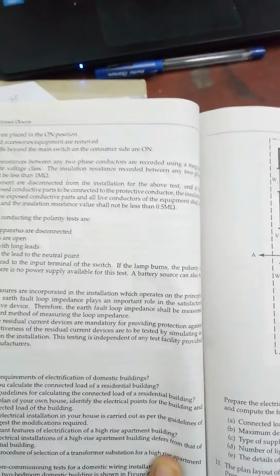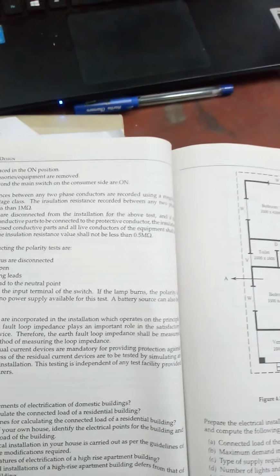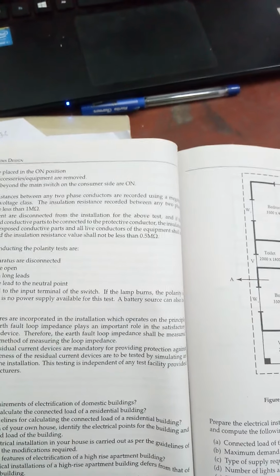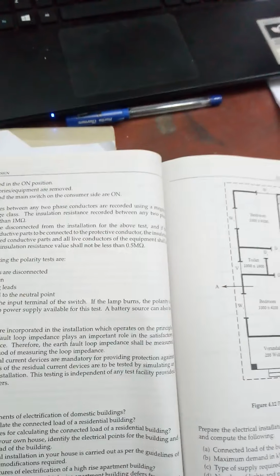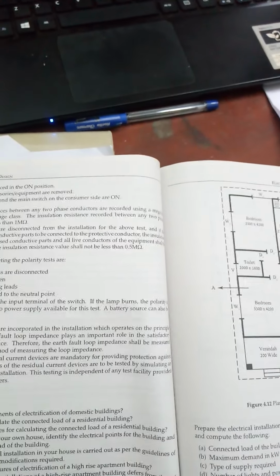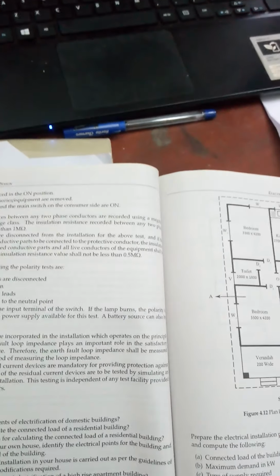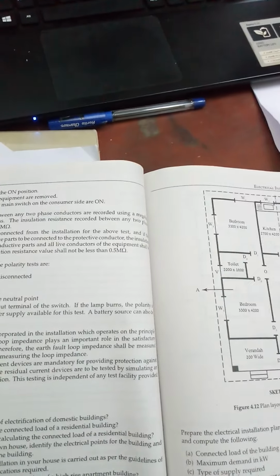When protective measures are incorporated in the installation which operate on the principle of leakage current, the earth fault loop impedance plays an important role. Earth fault loop impedance is measured with the help of a loop impedance meter, the standard method of measuring the loop impedance. In installations where residual current devices are mandatory for providing protection against indirect contact, the effectiveness of residual current devices can be tested by simulating an artificial fault condition on the installation. This testing is independent of any test facility provided on the device by the manufacturer.